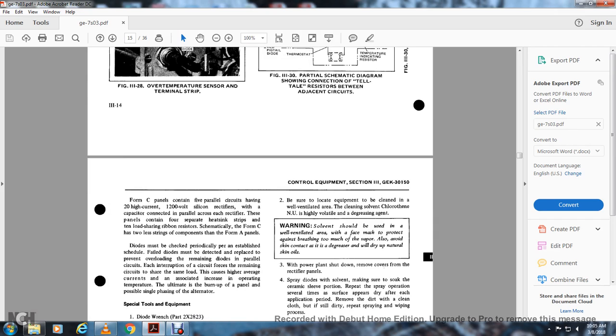Form C panel contains 5 parallel circuits having 20 high current, 1200 volt silicon rectifiers, with the capacitor connected in parallel across each rectifier. The panel contains 4 separate heat sinking strips with 10 load sharing ribbon resistors. Schematically, form C has two less strings of the components of the form A panels.